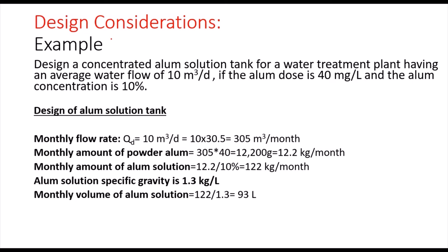Now let's see a practical example of how I can design an alum solution tank. We have to design a concentrated alum solution tank for a water treatment plant that has an average flow rate of 10 cubic meters per day. The alum dose is 40 milligrams per liter, and we can get this value using a jar test.